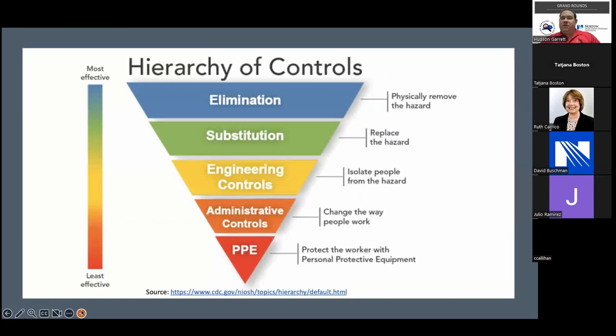Part of this is getting down to the hierarchy of controls. At the very top are the most effective interventions, where we eliminate the risk. An example: you're using a reusable laryngoscope and doing low-level disinfection, which isn't even correct—you should do at least high-level—and you move to sterilization. That eliminates the risk as long as you do sterilization correctly.